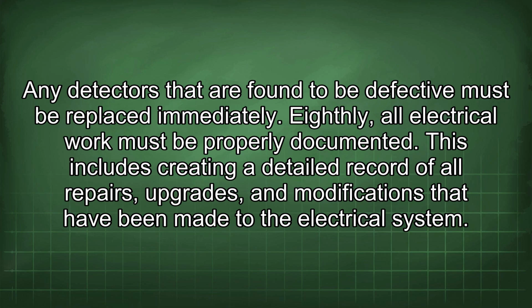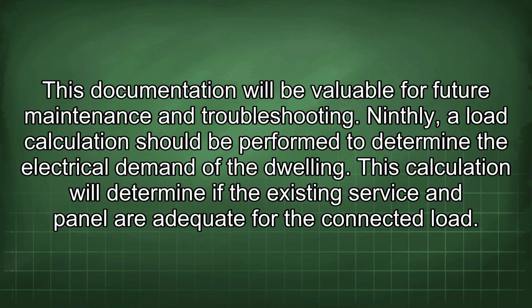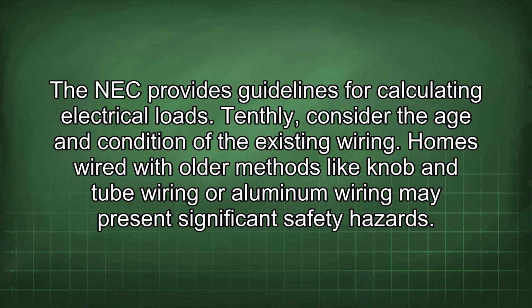Eighthly, all electrical work must be properly documented. This includes creating a detailed record of all repairs, upgrades, and modifications that have been made to the electrical system. This documentation will be valuable for future maintenance and troubleshooting. Ninthly, a load calculation should be performed to determine the electrical demand of the dwelling. This calculation will determine if the existing service and panel are adequate for the connected load. The NEC provides guidelines for calculating electrical loads.